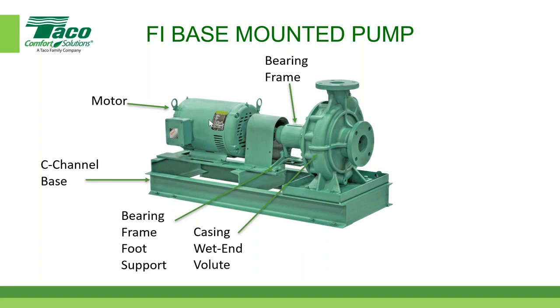And for variable speed applications, and let's not kid ourselves, that's 90%+ of the market nowadays, if not higher, especially above 5 horse, I think it's required in the States and in Canada as well, they're going to have a drive on it. And there's a good possibility, if there are some internal system issues, wiring, not enough grounding in the building or whatever, that that drive could cause issues with the motor. And that will affect the warranty, and it really, really gets messy.